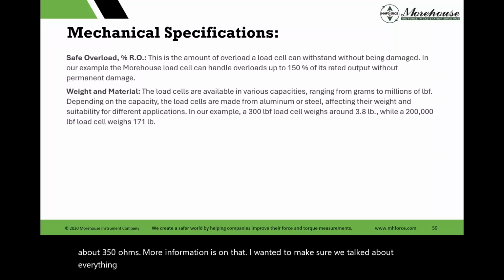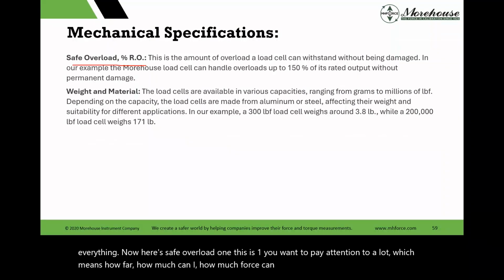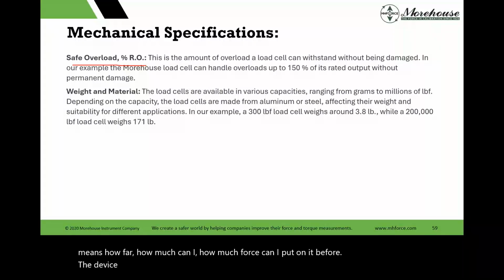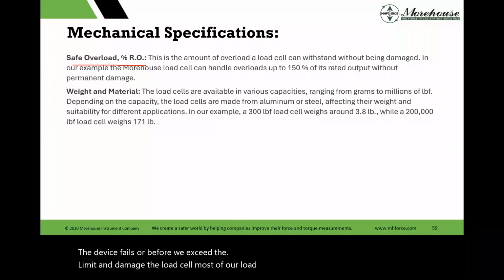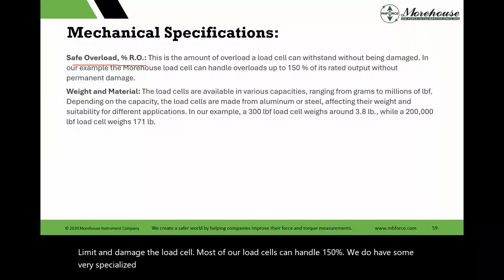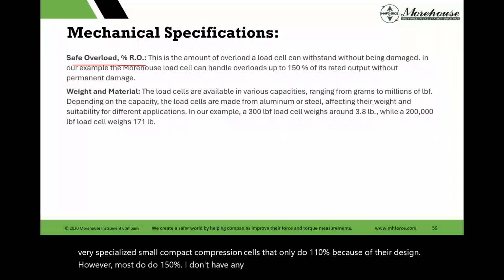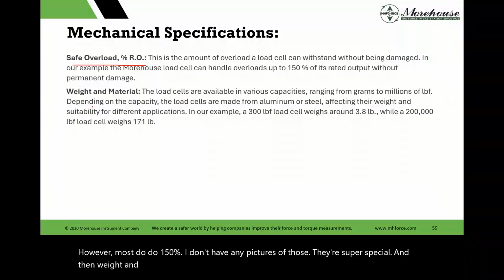Now here's safe overload. This is one you want to pay attention to a lot, which means how much force can I put on it before the device fails or before we exceed the limit and damage the load cell. Most of our load cells can handle 150%. We do have some very specialized small compact compression cells that only do 110% because of their design. However, most do 150%. I don't have any pictures of those. They're super special. And then weight and material. How heavy is it, right?